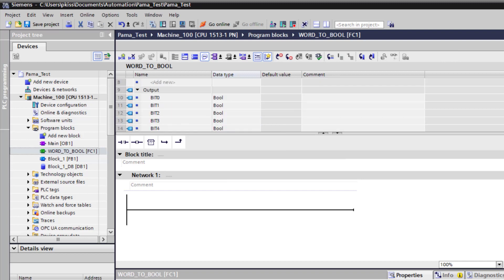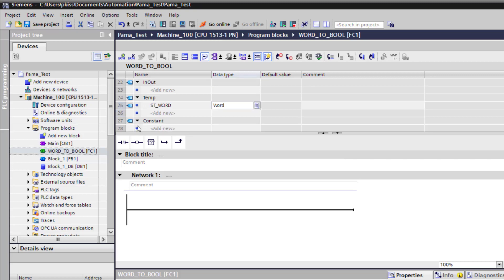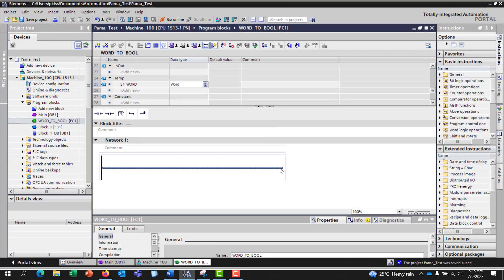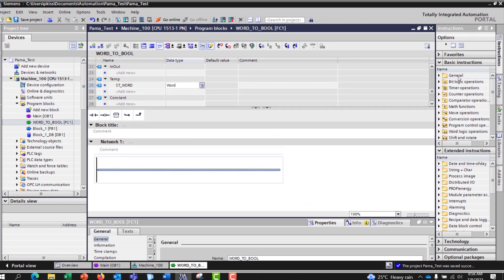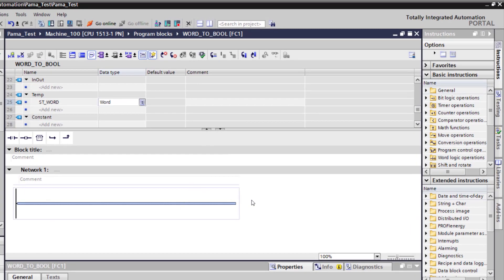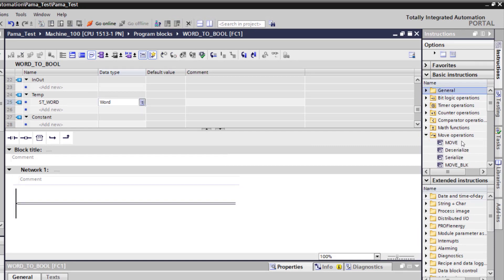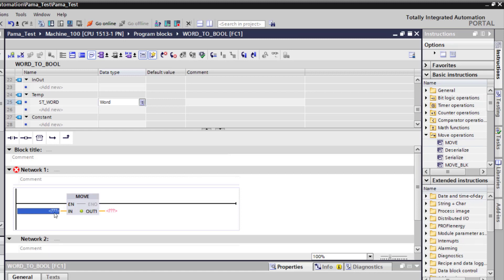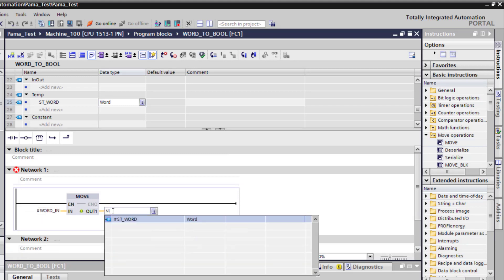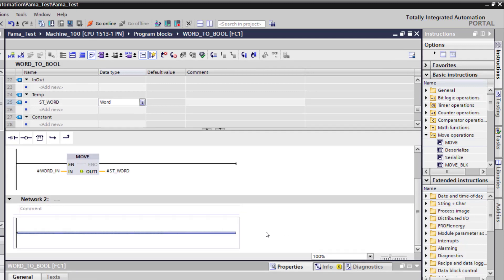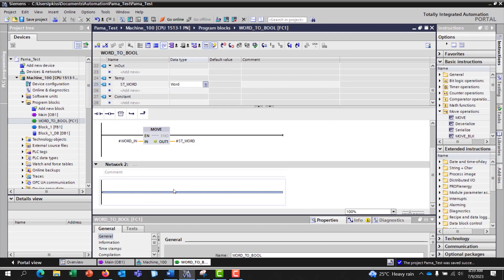I have all my variables: my input, my output bits, and my temp. I need to create the first logic — I need to move the input word into my temp word. So my input is going to be 'word_in' and the output is going to be my temp, that is 'st_word'. Now I create the logic to split the word into bits, and this is where the magic happens.